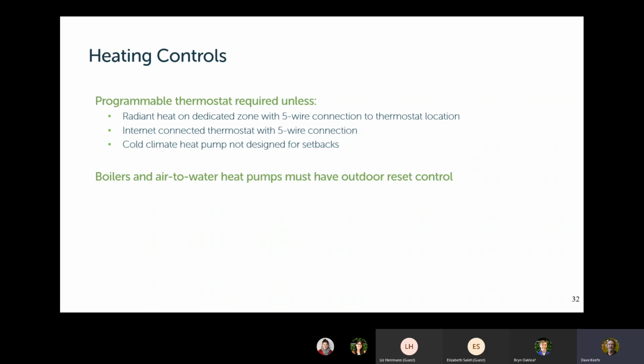And boilers and air-to-water heat pumps must have an outdoor reset control. Outdoor reset simply means there's a thermometer outside, and there's a control that varies the temperature of the distribution loop according to how cold it is outside. So if it's not very cold, they're circulating water that's not very hot. And as it gets colder and colder outside, they circulate water that's hotter and hotter.